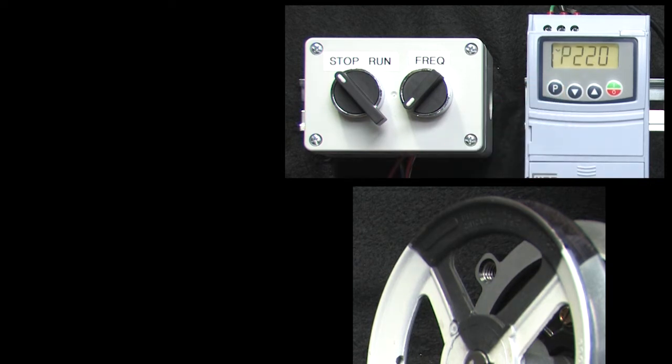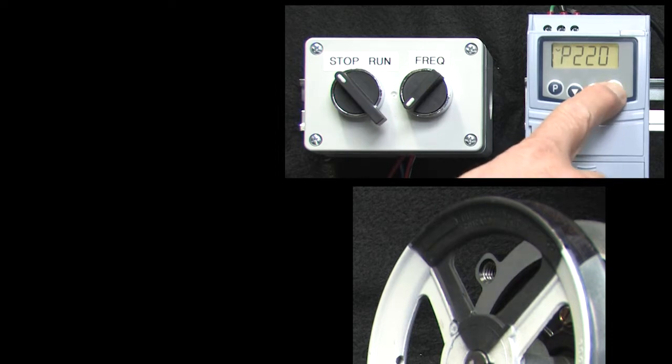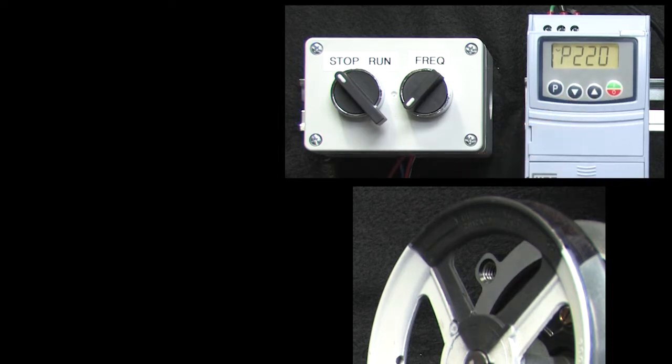Now the drive will power up in remote mode and if you don't change the other factory defaults that means you'll no longer be able to start the drive from the HMI keypad.